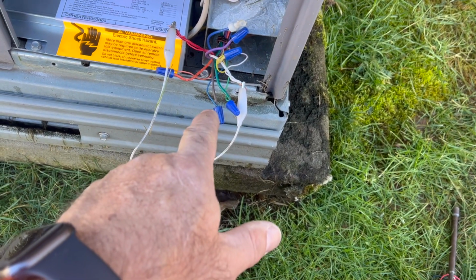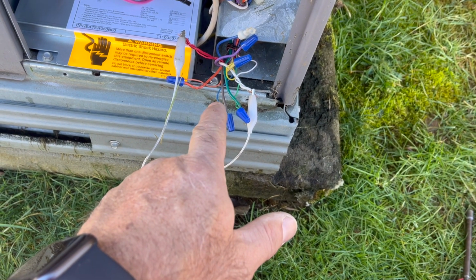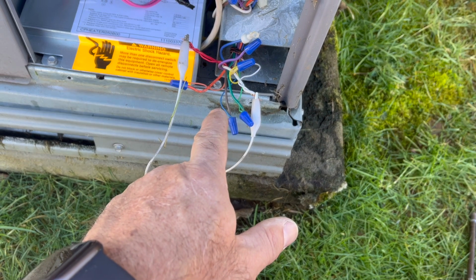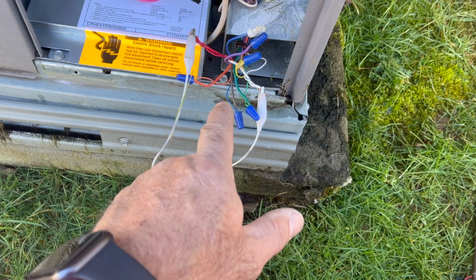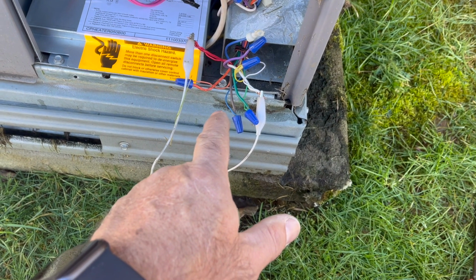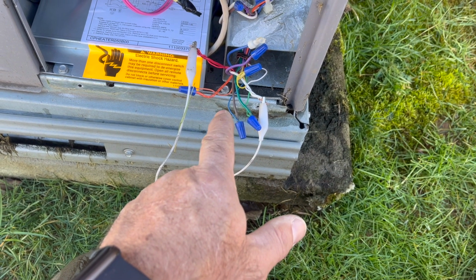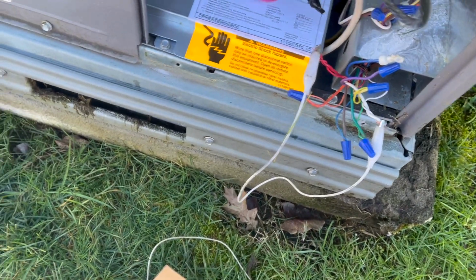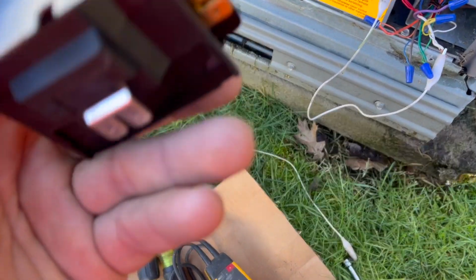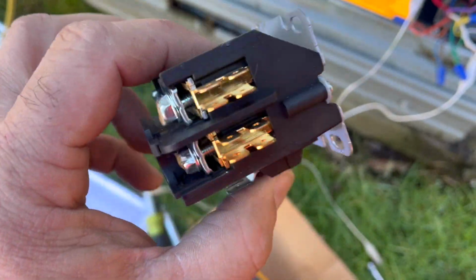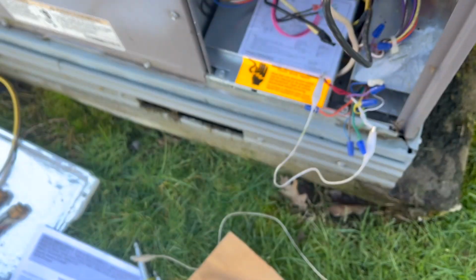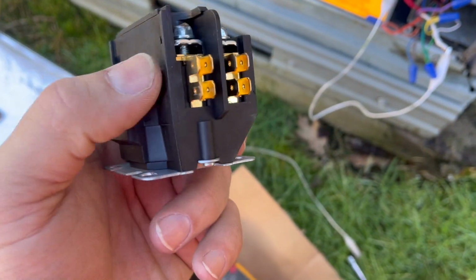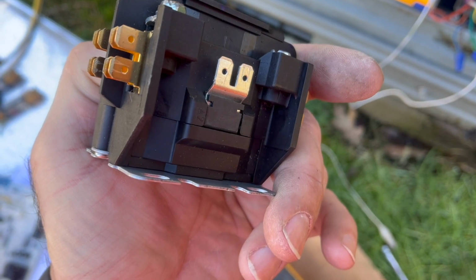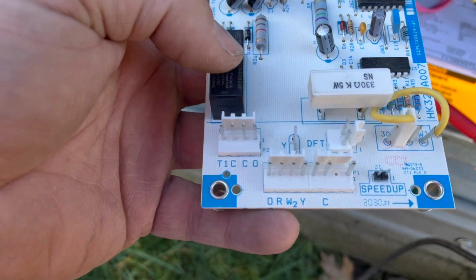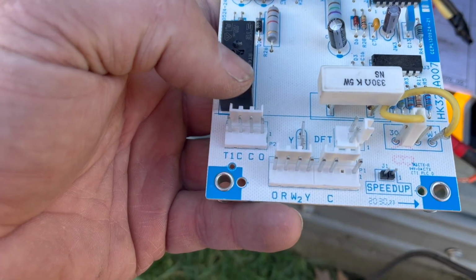So the reversing valve is 24 volts, and it wouldn't have been on in heat mode unless it happened to be in defrost. So before I leave, I'll go ahead and ohm out the coil on the reversing valve to make sure it's not like that contactor. Yeah, you can't see none of this contactor without taking it apart, but I can smell it. I guarantee you it's black inside. And to keep from having to open that compartment up, I already opened it and checked for rubs yesterday when I was up here.